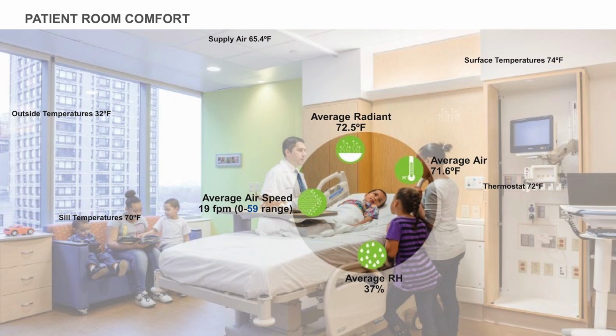to understand what we are actually operating at. Are people comfortable? Are they not? How do they actually match with this model? And what are some of the things that we're observing where things deviate? Interestingly, one of the things that we noticed in almost every space that we went to, where things deviated from the acceptable norm of comfort, was actually the airspeed. Where we placed the diffusers, because we have such large air volumes, often created perceptible drafts that were further exacerbating these problems of comfort.